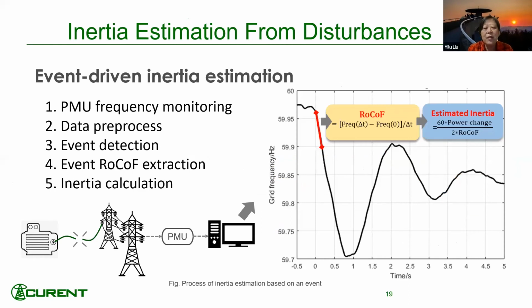So one contribution or benefit of having those measurements is that I measure frequency and I also measure angle. Now this is not power factor. This is not power factor angle. It's not between your real or reactive power. This is the angle between two locations. This is the power angle. It determines the flow of real power. So I measure the angle and I measure frequency, which allows me to determine and find out system inertia. And how do I do that?